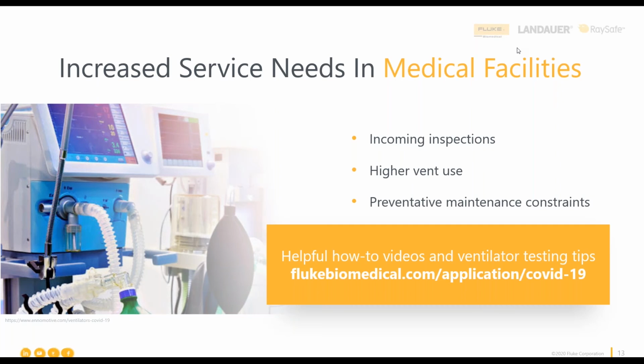And at that point, the hospital needed to carry on and do some additional testing. Incoming inspections was really a critical thing to do. Trust but verify. And especially where you had a non-traditional manufacturer delivering a product, a ventilator that you had not seen before, that needed to be run through some paces before you put it into clinical use.